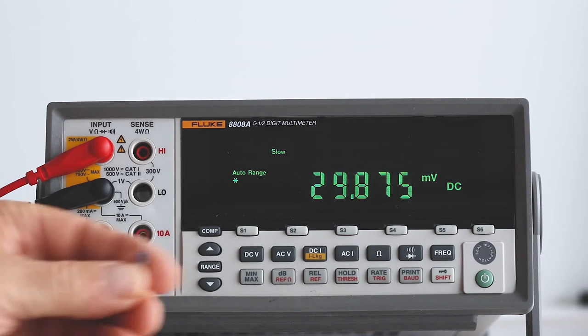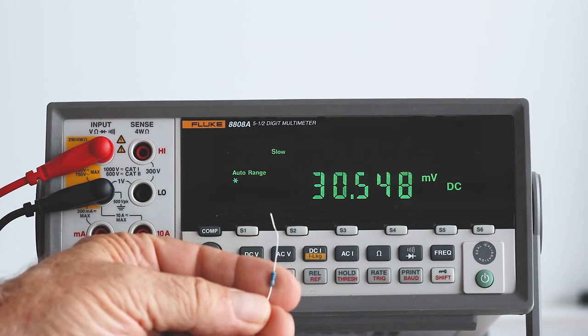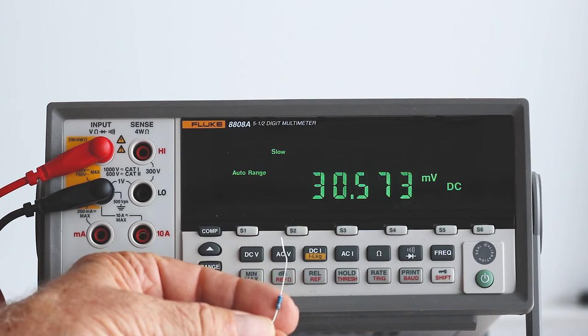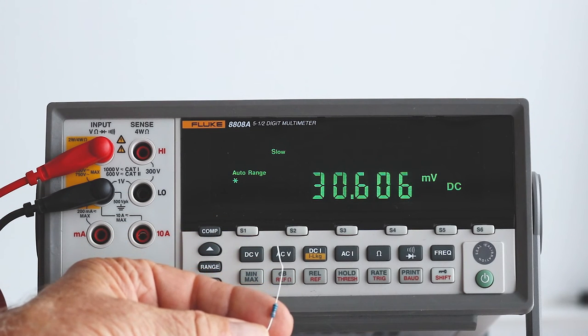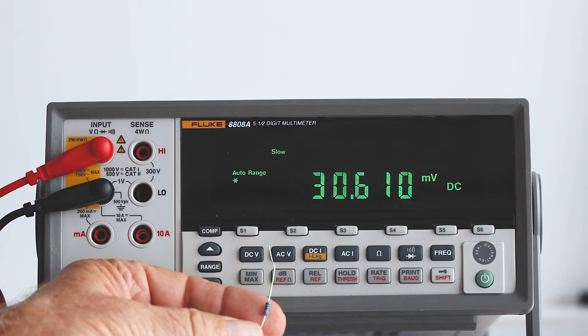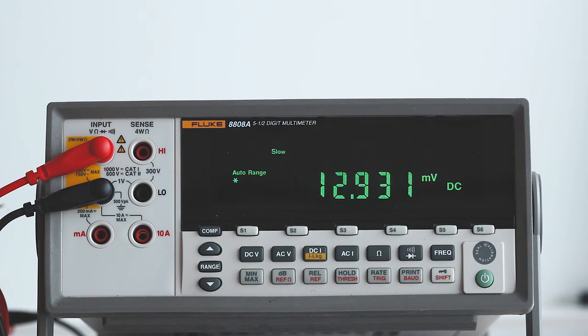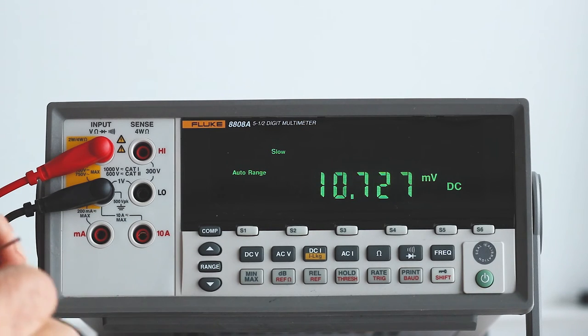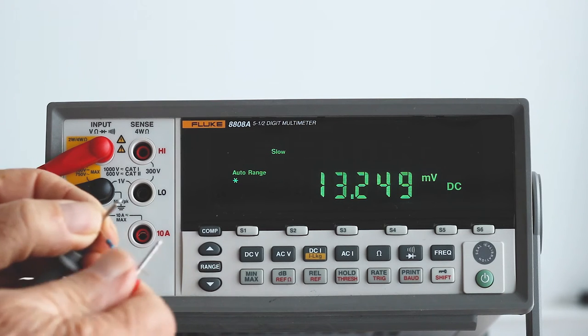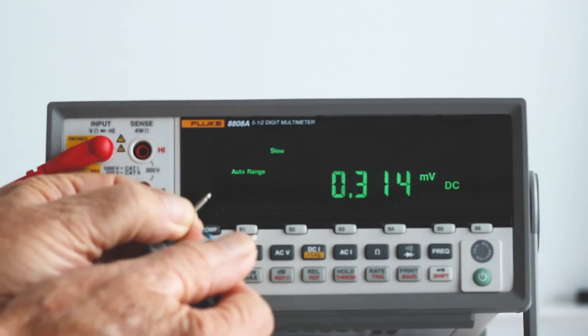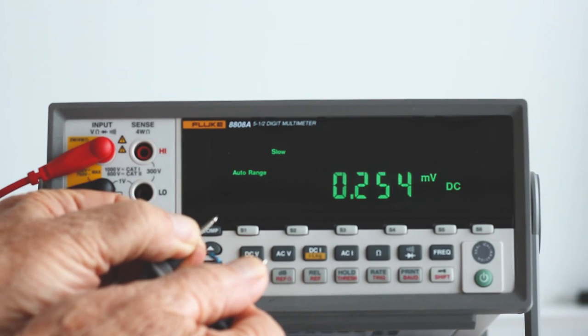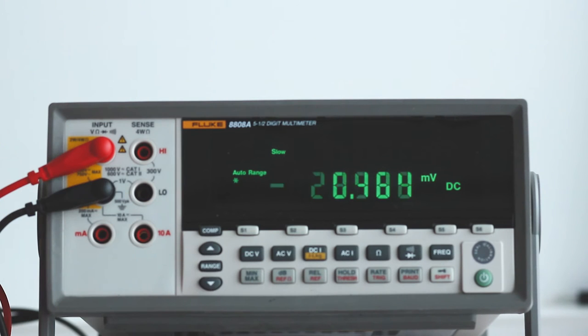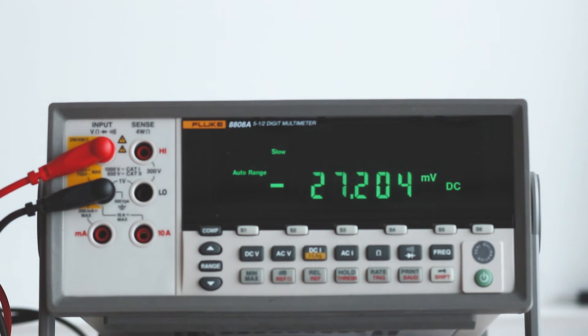If we shunt this 3000 ohm resistor across the probes, most of the phantom voltage is suppressed. You notice that it dropped down to a tenth of a millivolt.